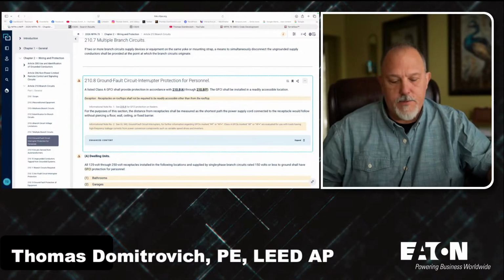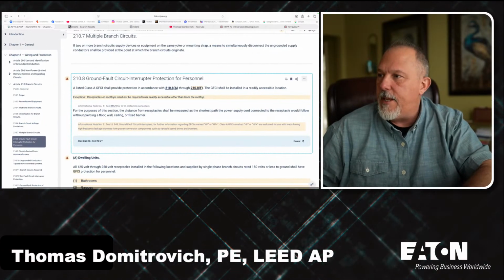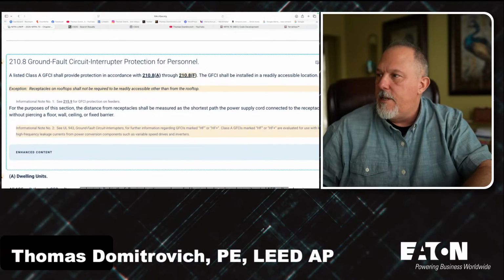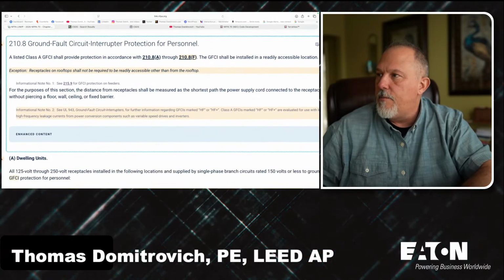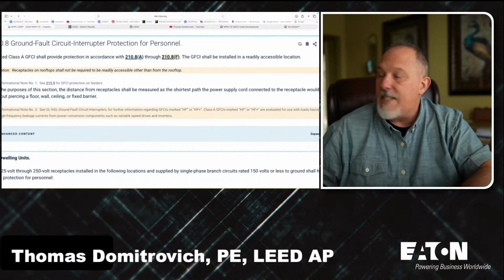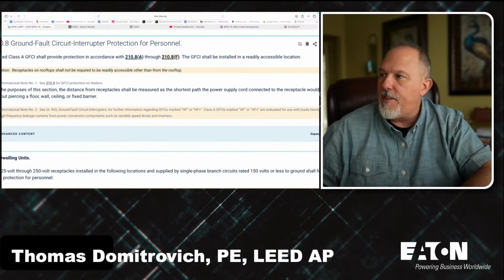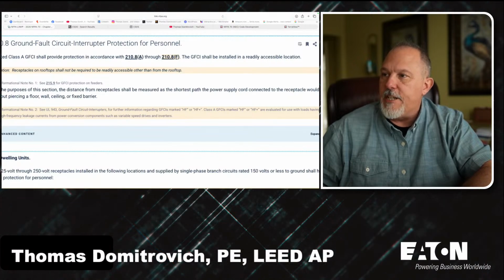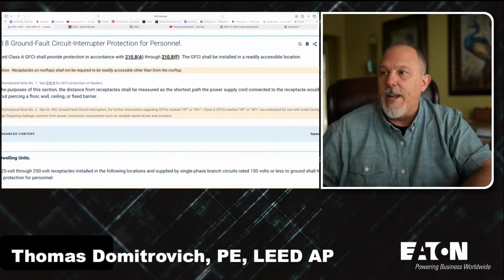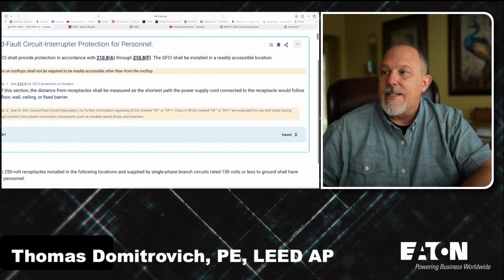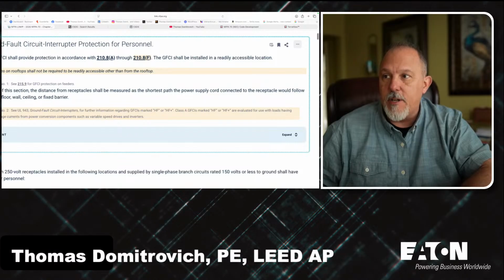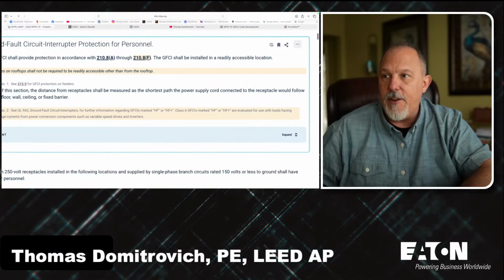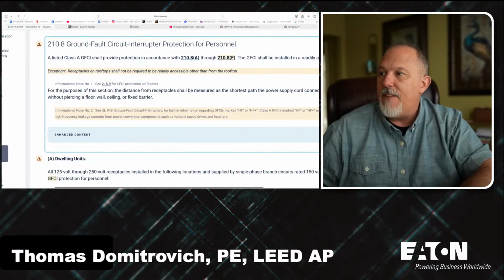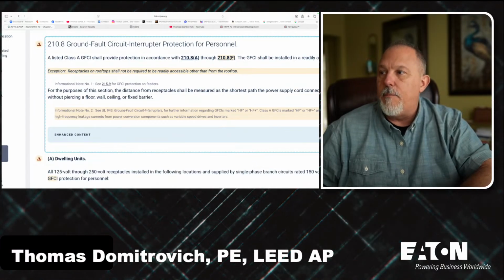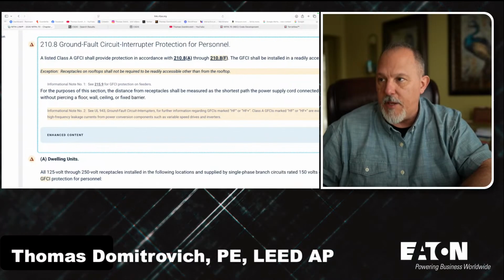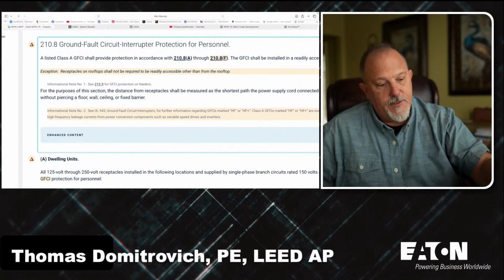If you get into your NFPA Link or grab your book, it's right here, informational note number 2. It says to see UL 943 for further information regarding GFCIs marked HF or HF plus. Class A GFCIs marked HF or HF plus are evaluated for use with loads having high frequency leakage currents from power conversion components such as variable speed drives and inverters.